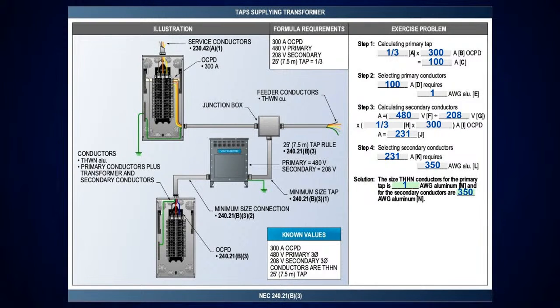1 aluminum conductor. And this is a trick question here, because what will happen if you're taking the test, you'll look at the conductors we gave in this case, and we're telling you we're using THWN aluminum instead of copper here. Okay? So you've got your first column, then you go over to the next set, you'll see the 60, 75, 90 degree C over there, and that'll be your aluminum conductors.